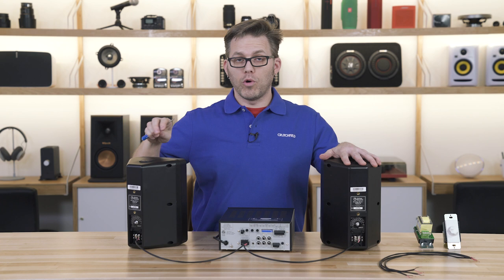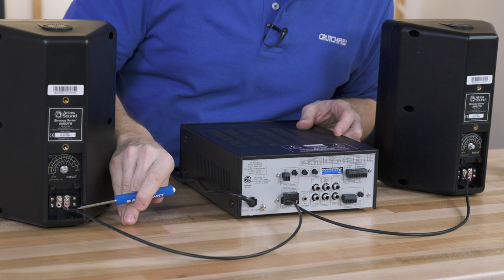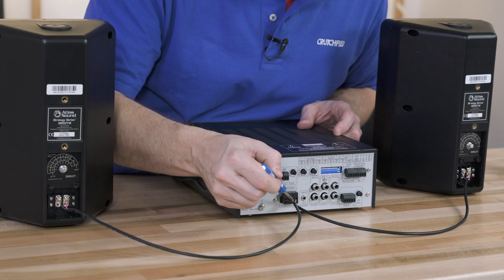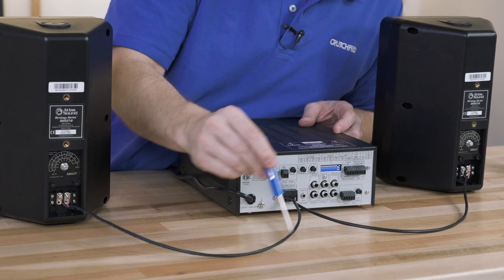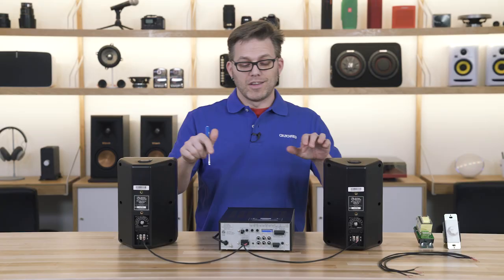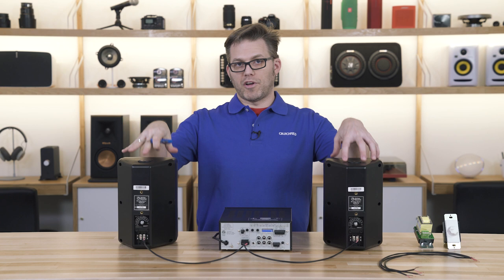All right, so now we've got our system still wired in parallel but with two home runs, one from one speaker, one from the other speaker, and we're just matching up that positive to the 70 volt, positive to the 70 volt, that's our red wire on each, and then the minus to our common on each of those two runs. Still in parallel, still able to control the volume of both speakers from one location.